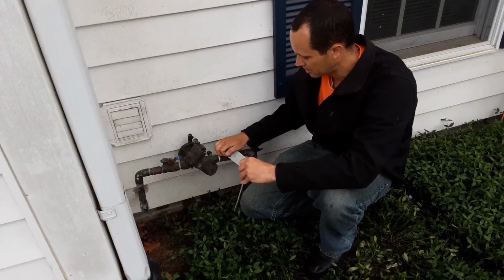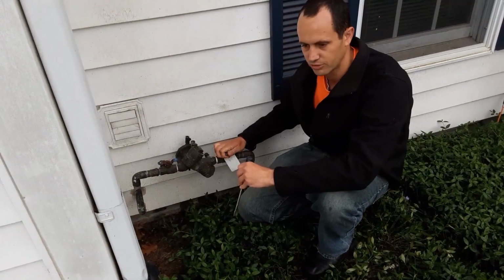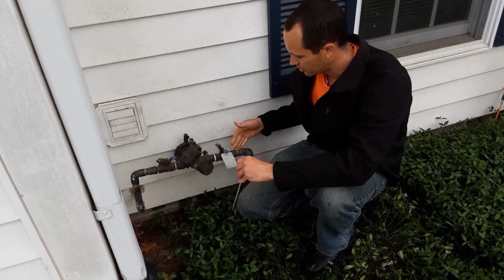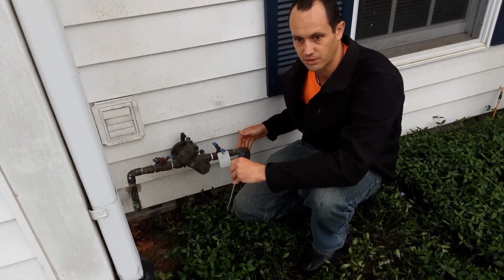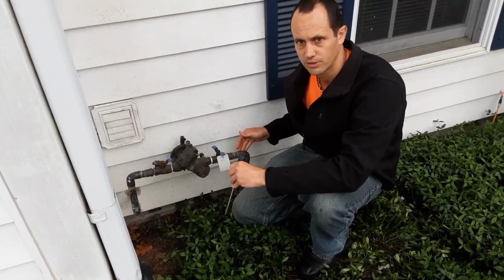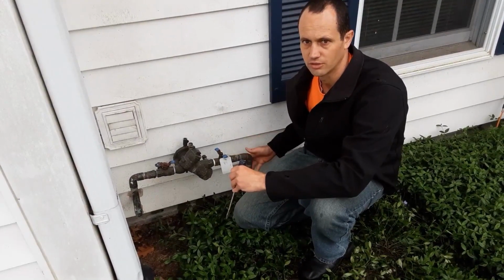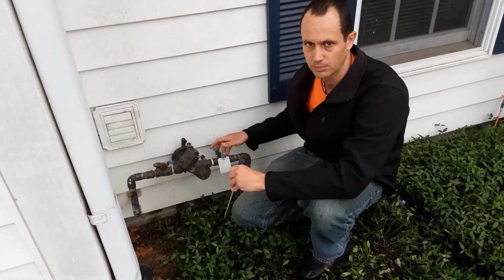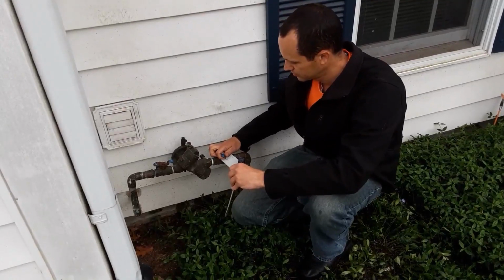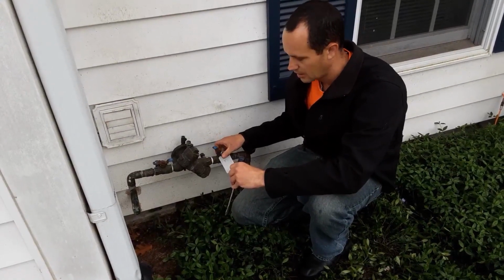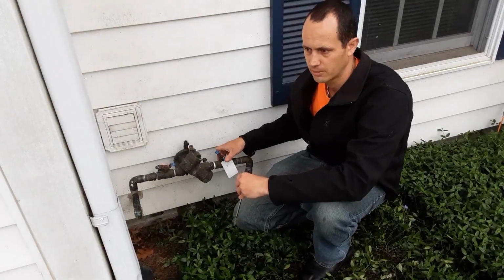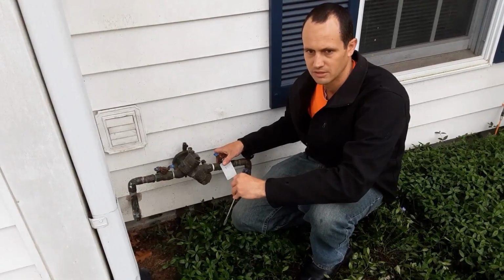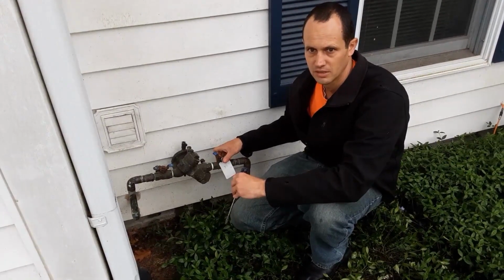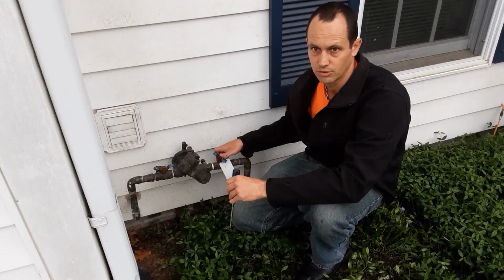After this is pressurized, I'm going to slowly open the valve on the other side, and this is going to allow water to enter the rest of the sprinkler system. Again, I want to open this valve slowly so the large slug of water doesn't slam through the system and break the pipes. I can hear the water traveling through the pipe, and when that sound stops, then I can open the valve the rest of the way. This might take just a minute, or it might take several minutes.